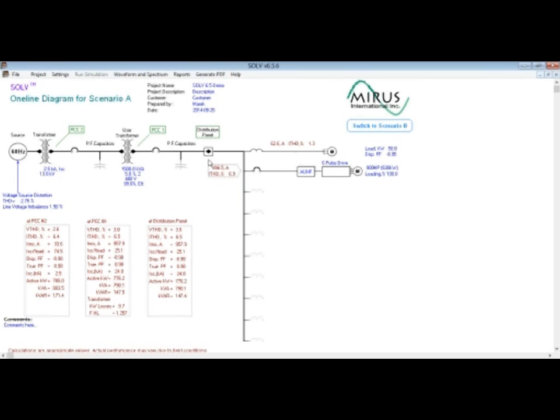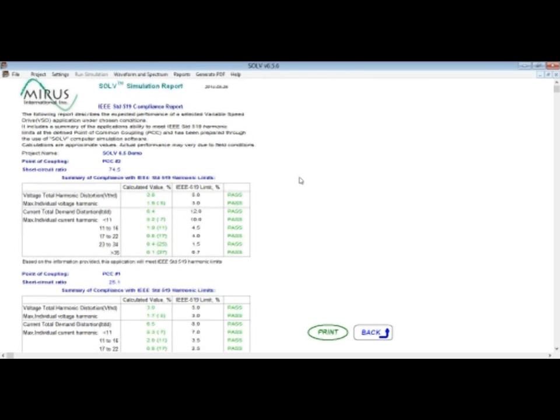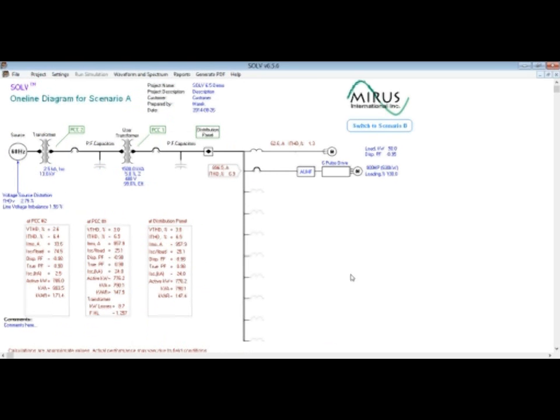and performance is much better than with 18-pulse VFDs. And viewing the compliance report, we can see that we still meet all required harmonic limits even with these pre-existing conditions. Having 2 scenarios calculated, we can view the comparison and energy report to compare the 2 solutions. So let's go to the comparison and energy report and see again.